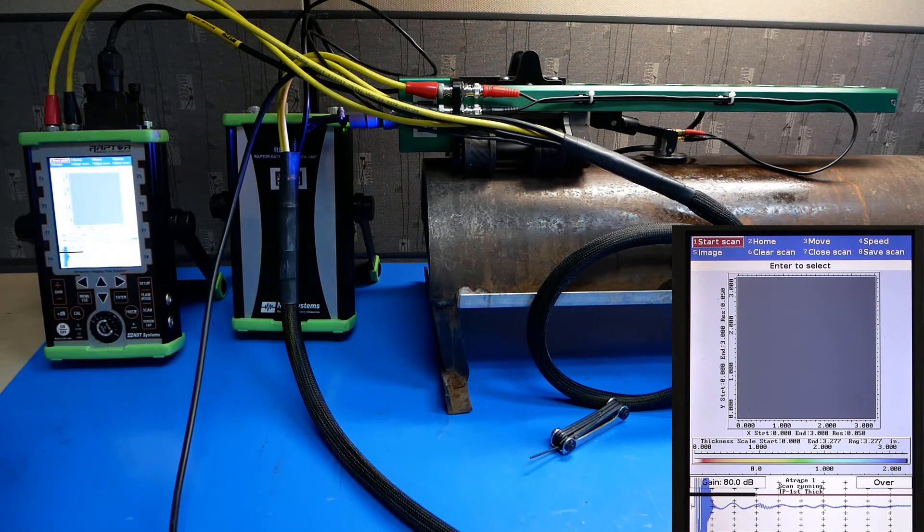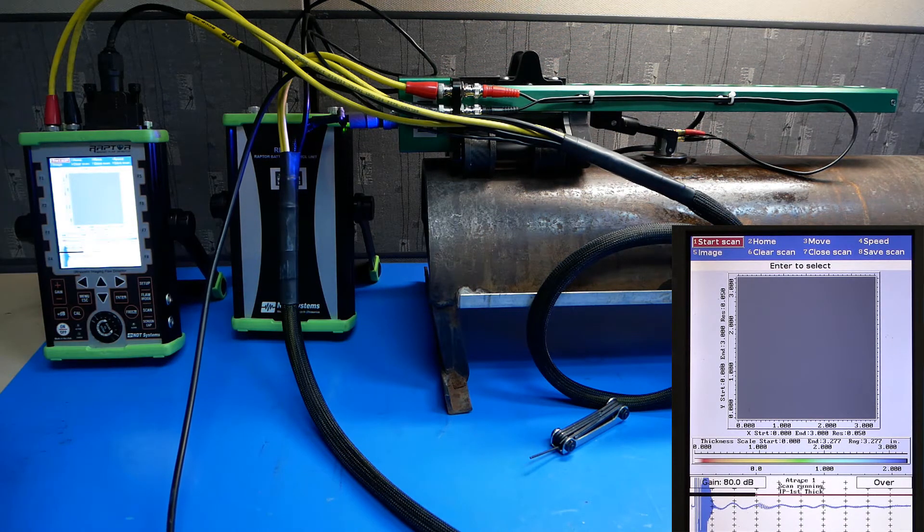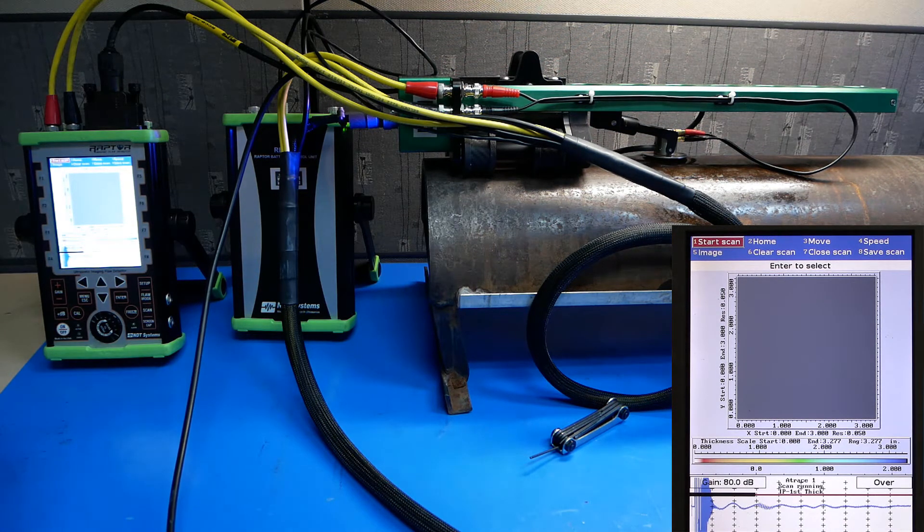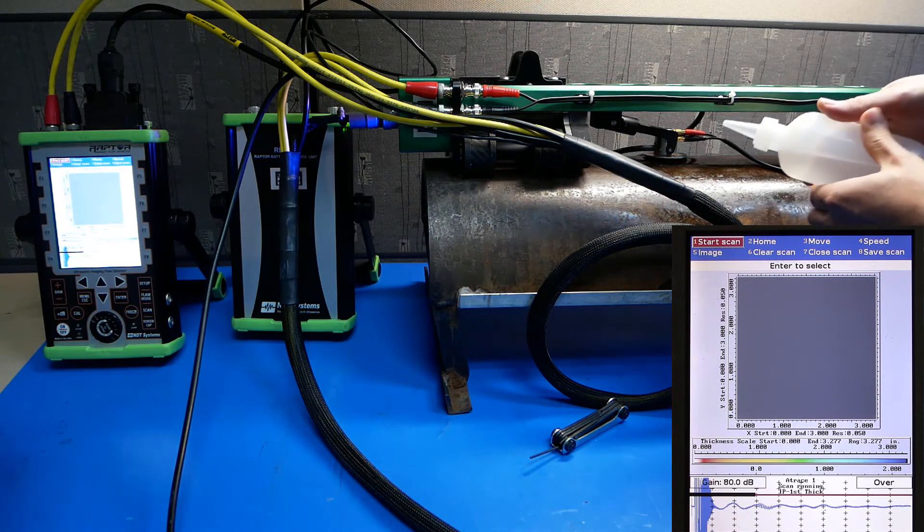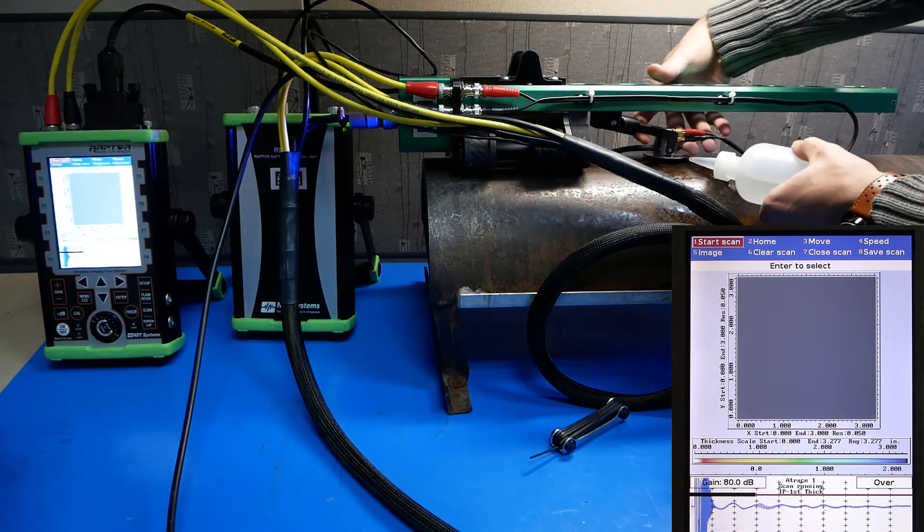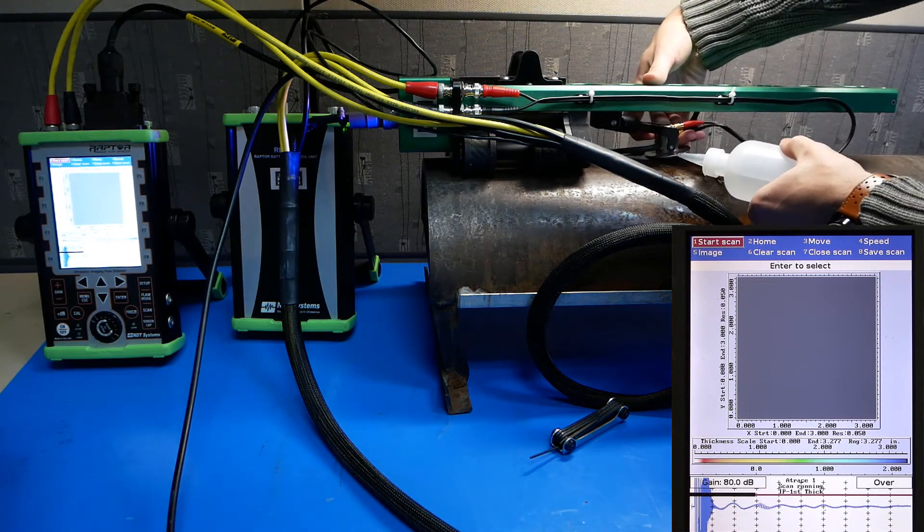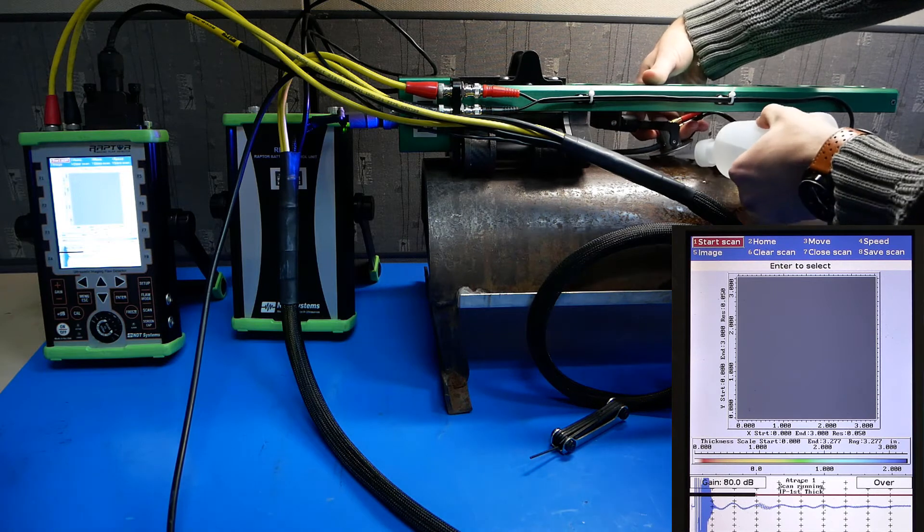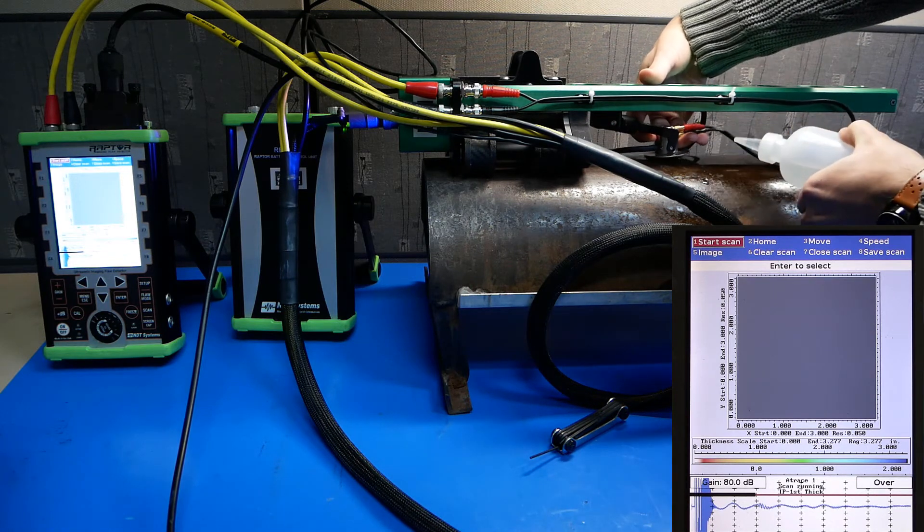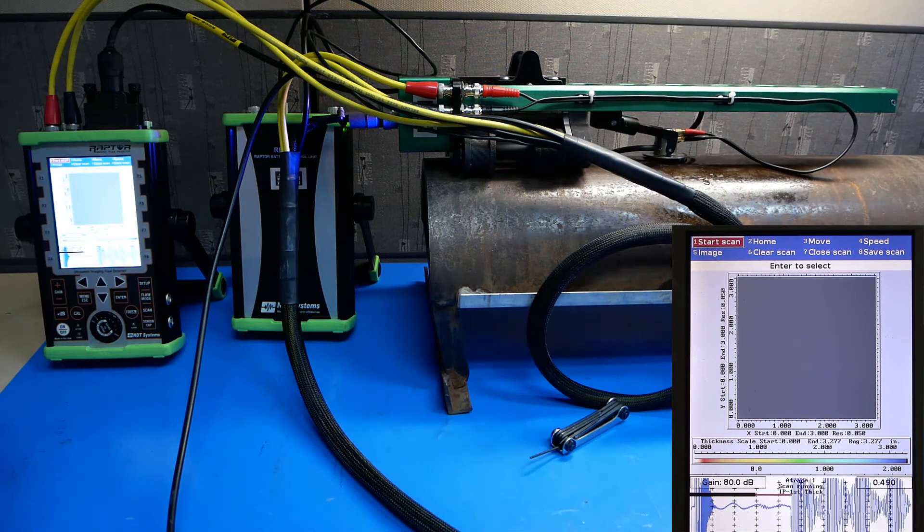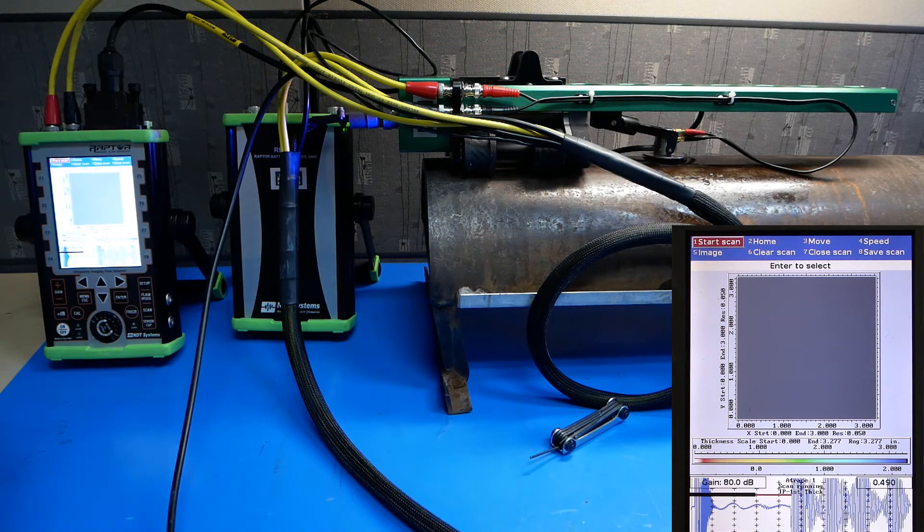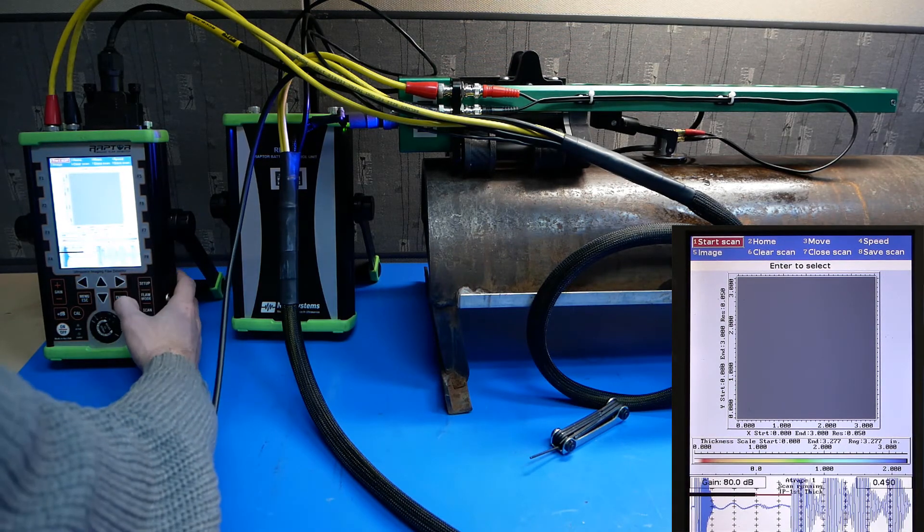Now, if you have a couplant feed system, go ahead and activate it or you can go ahead and put a little couplant in between the probe and the test material like so. Now you're ready to scan. Push start scan and wait for the results.